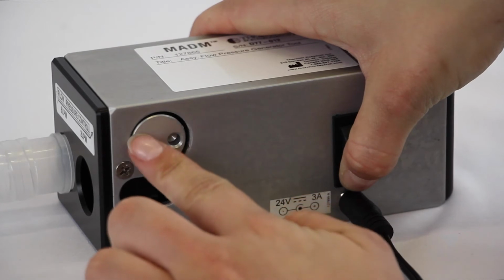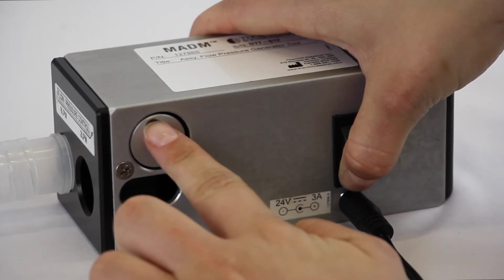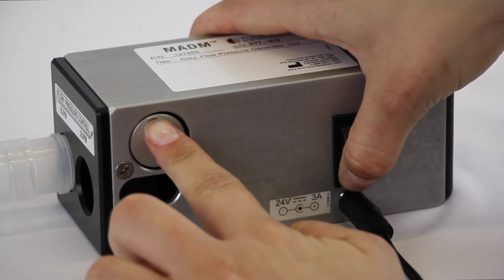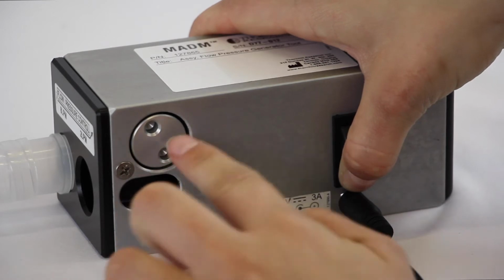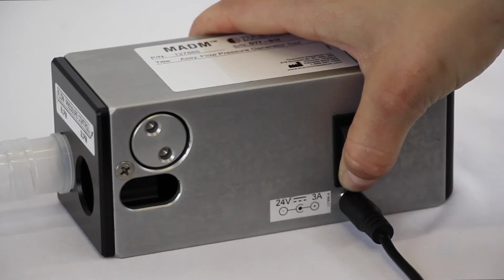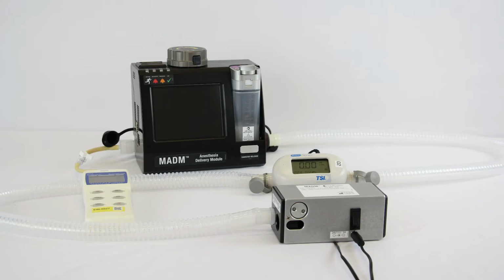Begin by pressing and holding down the activation switch on the adjustable flow source. While holding down the switch, use the control dial to adjust the speed of the flow source. Adjust the speed until the pressure meter reads approximately 50 centimeters of water. Ensure that the flow, measured by the flow meter, is less than or equal to 0.5 liters per minute. Otherwise, there may be a leak in the system.